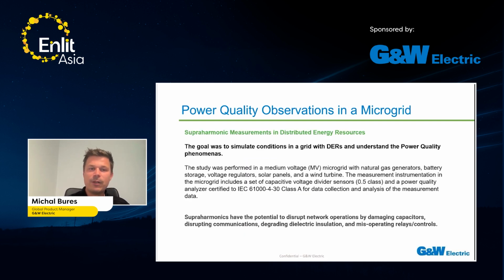So what we did, we would like to measure supraharmonics in the DERs. The goal was to simulate the conditions in a grid with DERs and understand the power quality phenomena. For the measurement, data analysis and collection, we use our AccuSense sensing technology, the voltage sensor, with 0.5 accuracy class, and a power quality analyzer. As we already know, supraharmonics have the potential to disrupt network operation by damaging capacitors, degrading the dielectric insulation, and causing relays to misoperate.